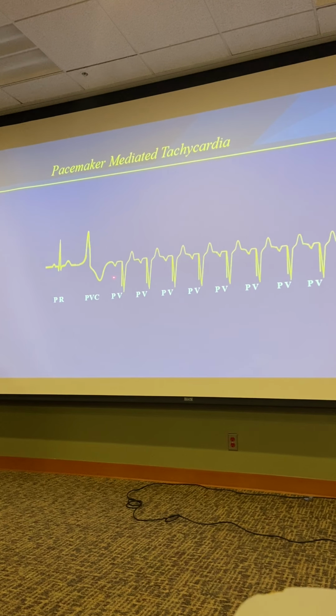Typically, this will occur at the upper tracking rate. So if the pacemaker is programmed to go from 60 to 120, you'll see this at 120. It doesn't always have to be at exactly that rate, but that's a very reliable, quick and dirty way to say, could this be a pacemaker-mediated tachycardia?